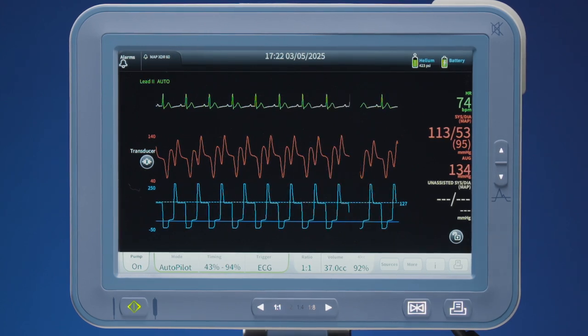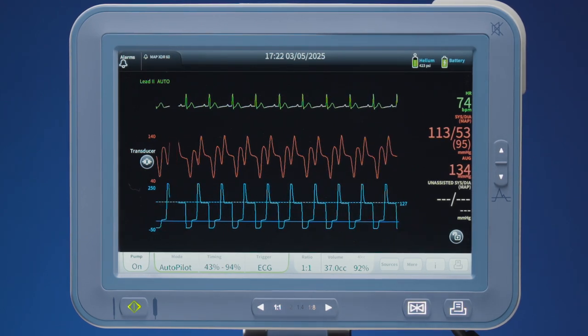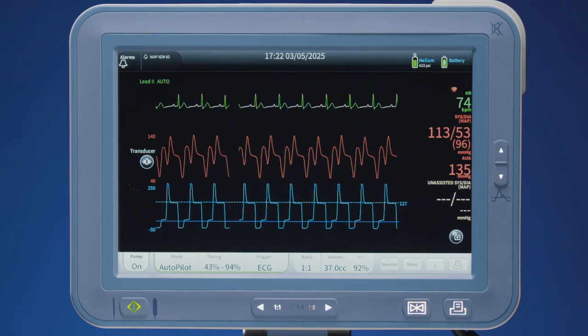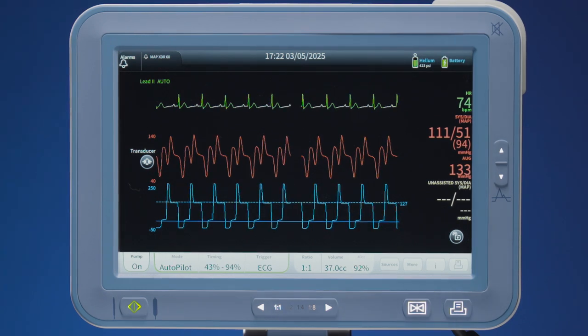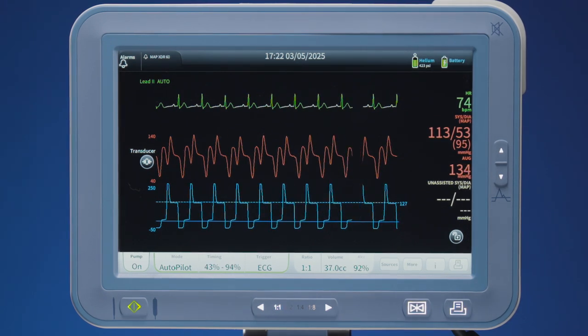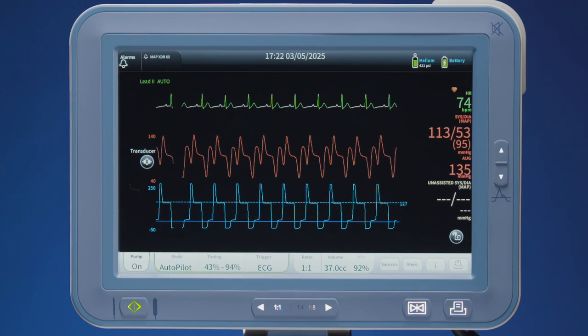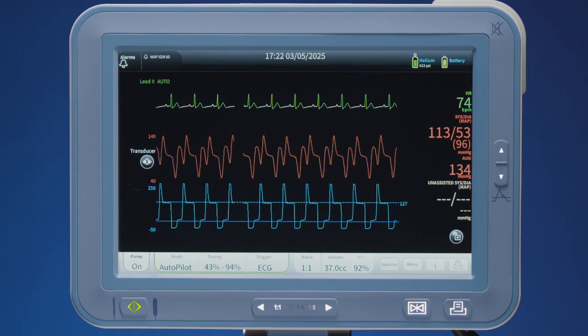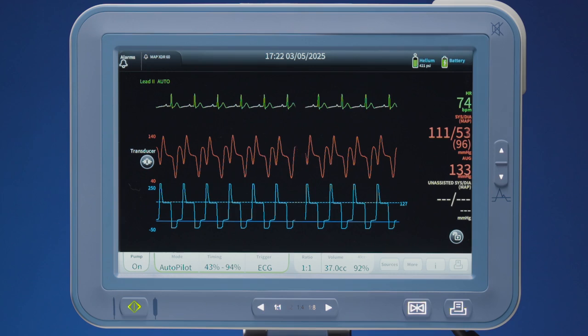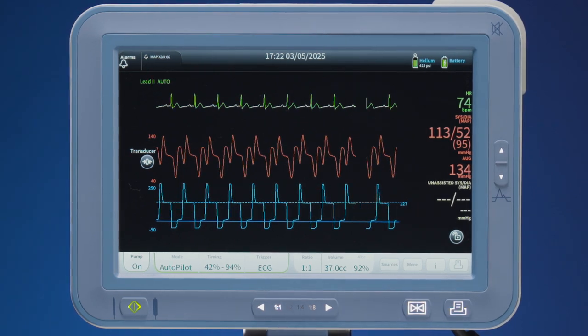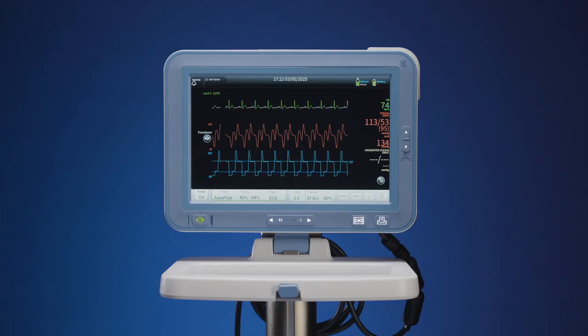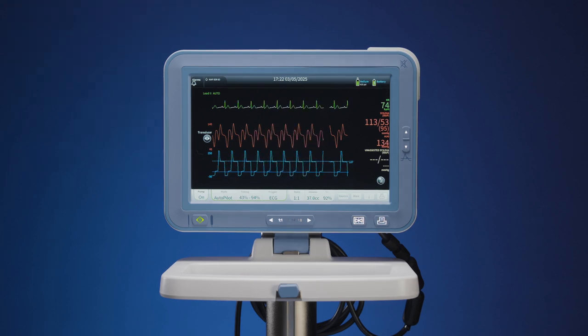The BPW height reflects the pressure in the aorta, therefore the plateau pressure on the BPW should be within plus or minus 25 millimeters of mercury of the augmented pressure. BPW width is approximately the duration in which the balloon is inflated. You may leave the cursor on the plateau pressure to continuously assess pressure changes. Should the plateau pressure be greater than 25 millimeters of mercury as compared to the augmentation pressure, this may indicate the balloon is too occlusive.